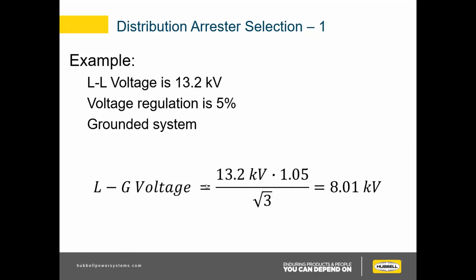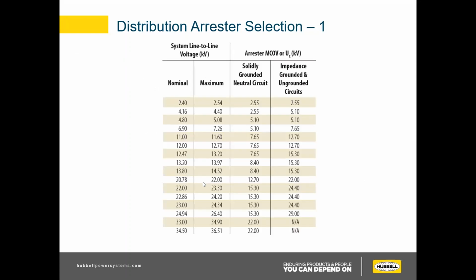So you will go to our catalog and find 8.4 kV in this column here, solidly grounded, neutral. Find 8.4 kV, or anything above 8.0, excuse me. So in this case, it'll be 8.4. A little trick here is this chart helps select. You have your nominal voltage and the solidly grounded. So it's going to be at 8.4.